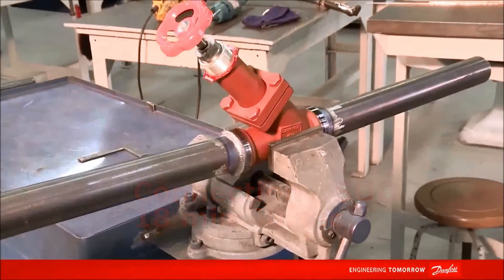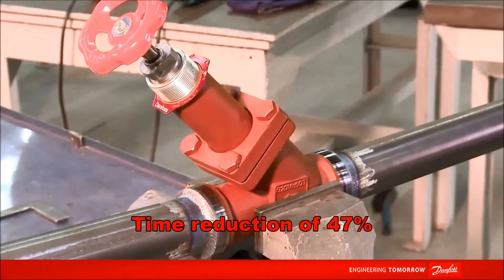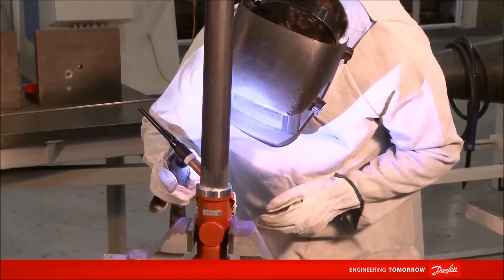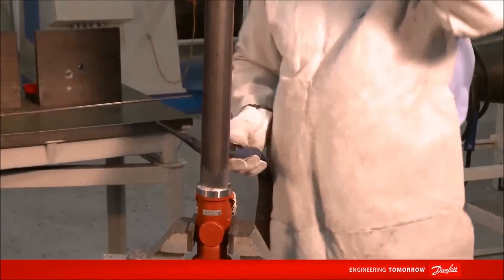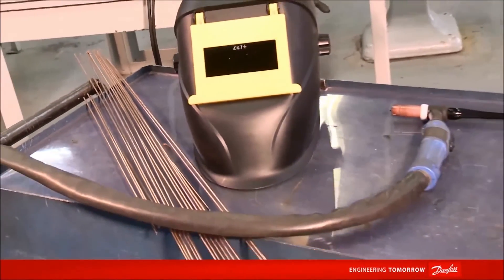Let's compare the two processes. As you can see, we saved over 16 minutes with the SOC connection. This was the time saved in a process performed on a workbench. However, this percentage may vary depending on the conditions of the facilities and the resources available. Besides the time saved in the installation process, we also economized on the welding material, avoiding waste from the pipe cuts during the preparation and allowing a better cleaning quality in the application.